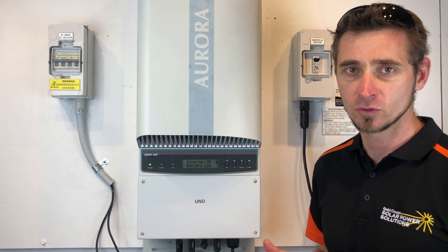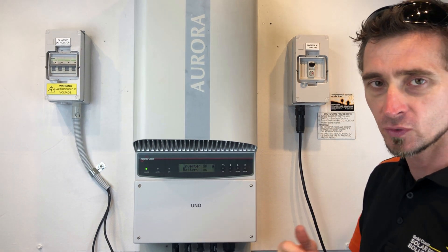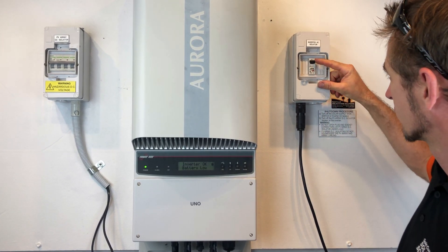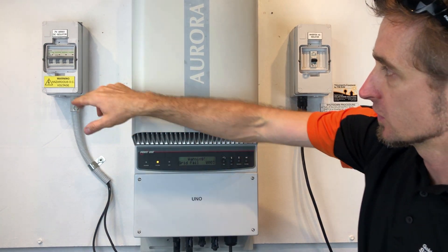The first thing we need to do is turn the system off, and it's always important you follow the shutdown procedure. Turn off the solar supply main switch — there'll be a switch located in your switchboard — or the inverter AC isolator. In our case we've got an inverter AC isolator here, so we're going to switch that one off.